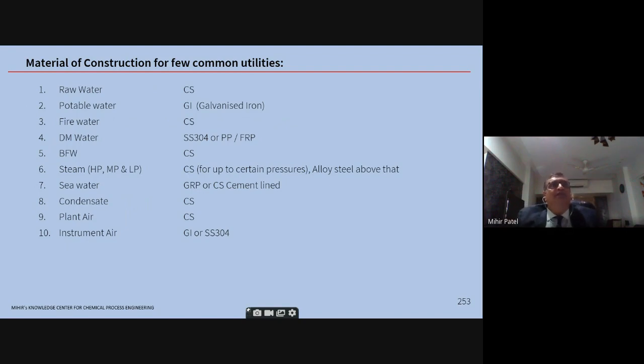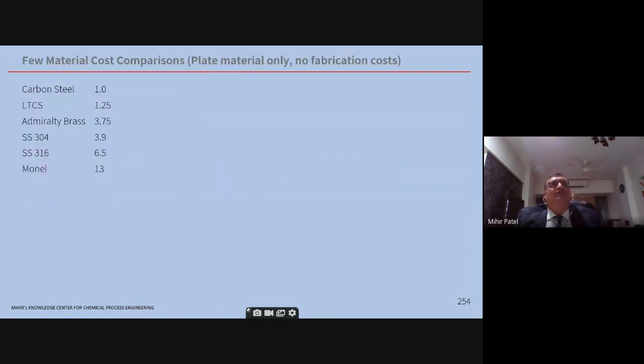So at the bottom you see instrument air is also GI. There is a chance of leakage occurring in union couplings because they are screwed fittings. So nowadays all major clients go with SS304 for the instrument piping also. Then the relative cost of the different grades you can see. Carbon steel, if you take it as one, just see at the bottom, SS316 is 6.5 times carbon steel. This gives you a relative idea.